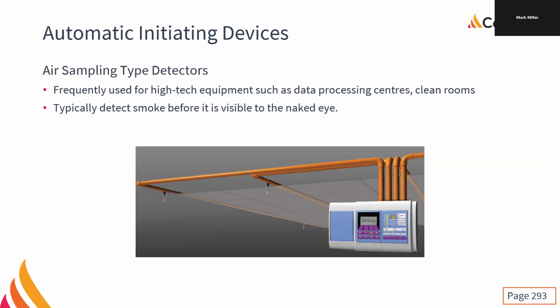Air sampling detectors. Very fancy, quite fun to install, really, really finicky to configure properly to get them working. They can be a giant nightmare. They're fun to install because, well, they get installed using blaze pipe. You know, that orange plastic sprinkler piping that you see sometimes. It gets installed by us, not the sprinkler fitters. And so, well, it's a fun change.